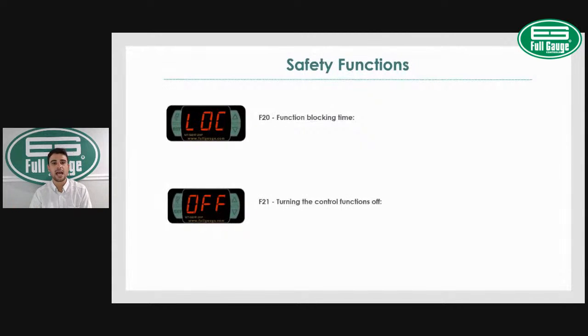And lastly, F21. That's turn on and turn off of the control function. So that allows you to turn the control into a simple thermometer. So let's say you don't want to use the control functions, you just set the F21 to off for maintenance, for example, or if you need to perform anything, instead of powering off the unit, you actually have the possibility to disable the relay output.